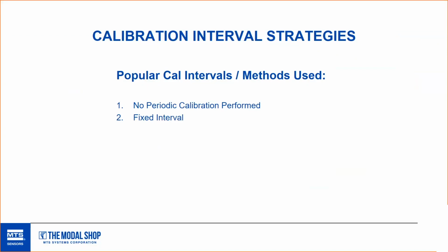Fixed interval: calibrated annually, every 6 months, every 24 months. This is probably one of the most common methods for sensors. Why? It's easy. Intervals are often given based on experience and history. If some sensors in a group start acting up, it's easy to reel in that interval time. Or the opposite: you can extend it if a sensor hasn't changed over several intervals. The downsides, of course, can include inadvertently taking bad measurements if the sensor performance has changed, so you might need to retest. And on the flip side, equipment may be calibrated too frequently, causing extra cost.